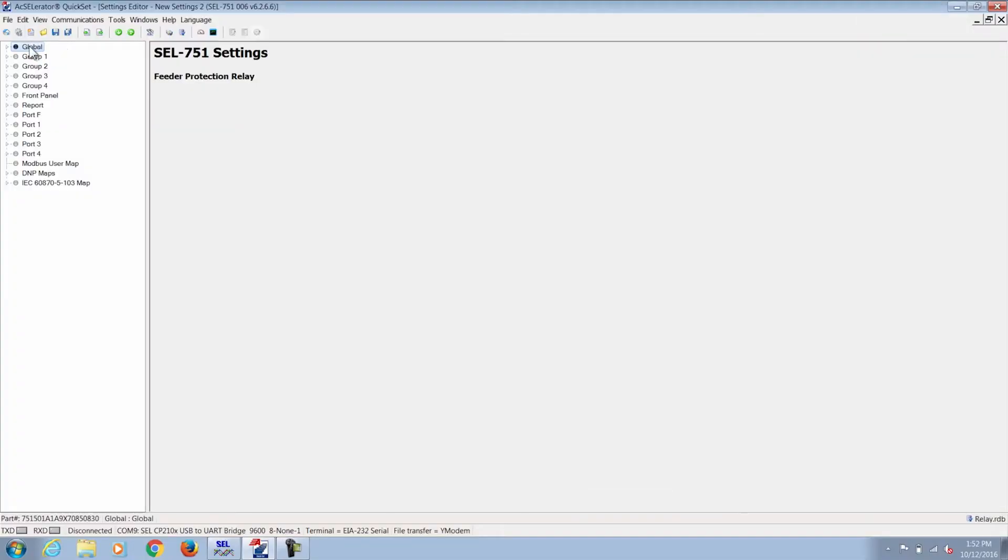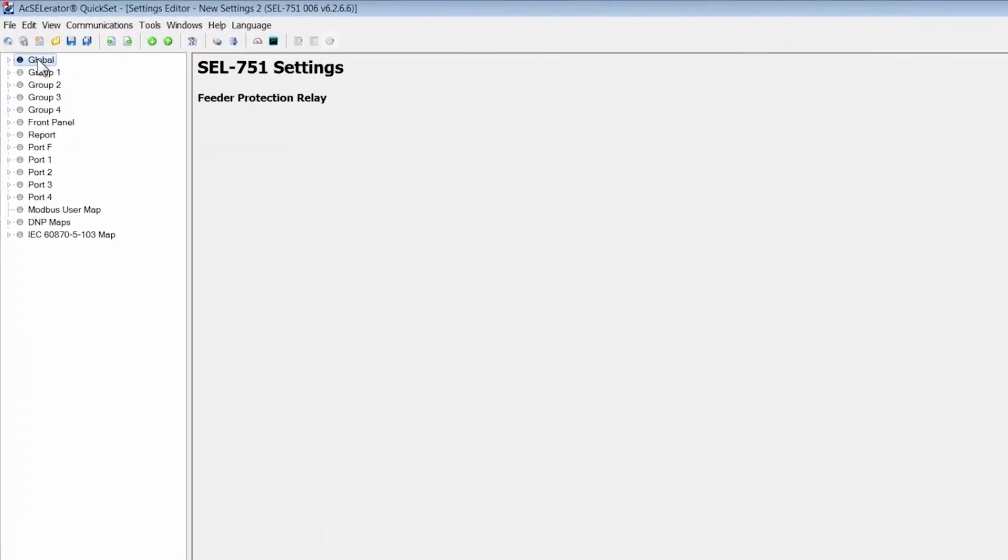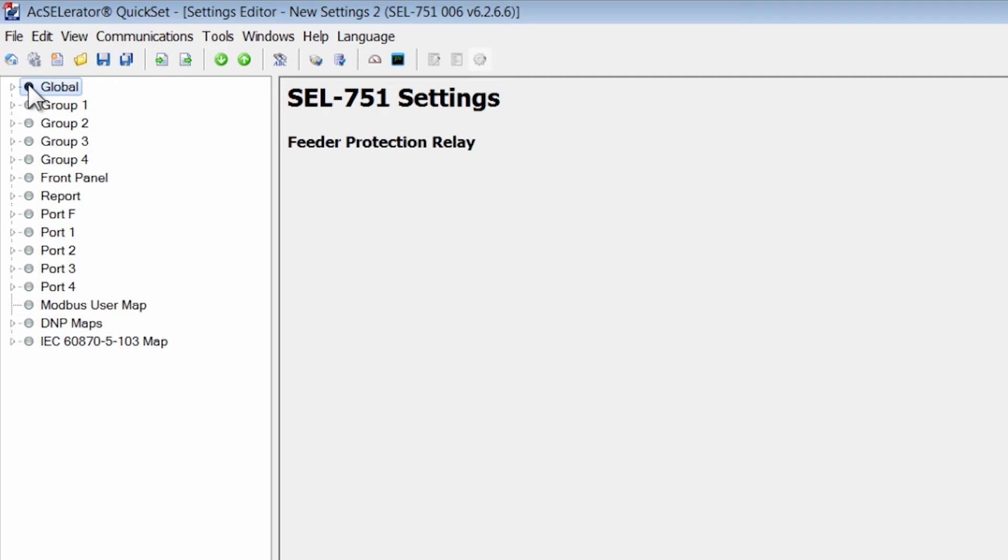Generally speaking, the settings are laid out in a tree structure format. The global is the overall settings that are impacting all of the other settings groups available in the settings file. We have four different groups available by default. The active group that needs to be programmed is group one. All the other groups are inactive.